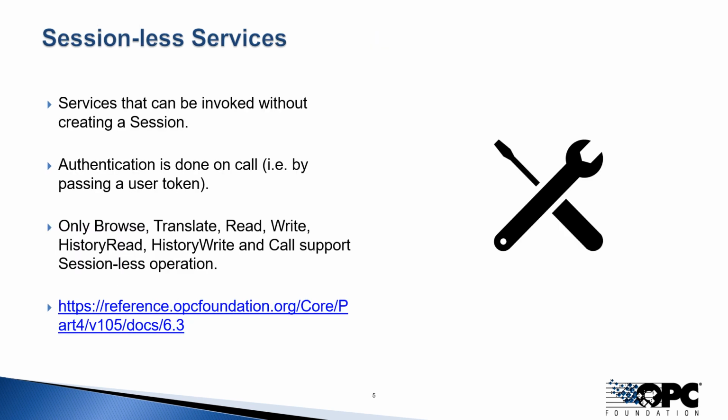However, traditional OPC UA services have sessions. And these sessions are important, especially when it comes to maintaining your subscriptions, and in particular, the change-based, the report on change mechanism, which is kind of core to how UA works, requires that the server keep track of what it had previously sent to the client. And that's a big chunk of state information that has to be maintained. But not everything that a UA server does has to be done with a session.